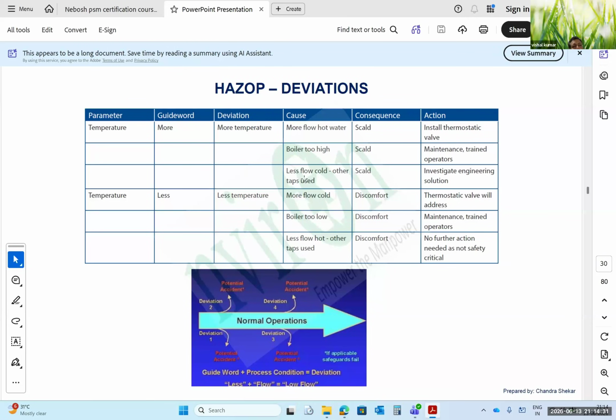Like, as I told you, the water system - this hazard study can be done only for the water system. Same can be done for the lubrication system, the gas system, or the steam system - what different types of gauges are there, what different types of PRV are there in the system. So for every system we have to do the HAZOP study and find out what deviations can take place for each parameter, and accordingly find out the cause, the consequences, and the action.